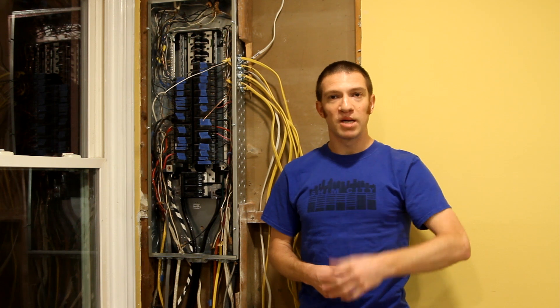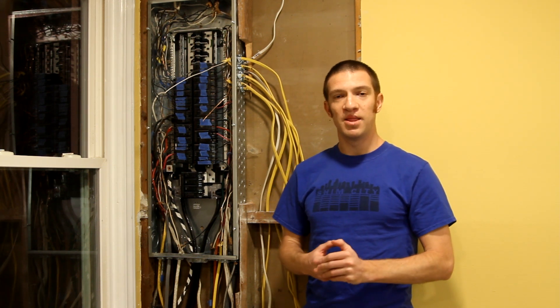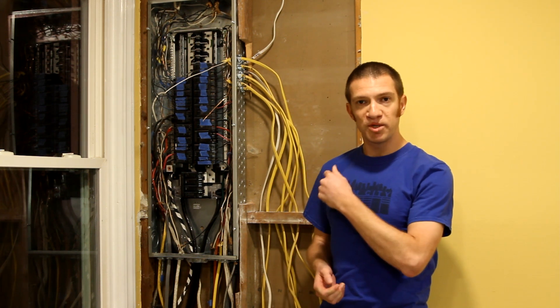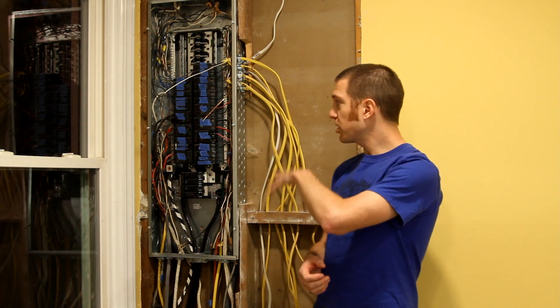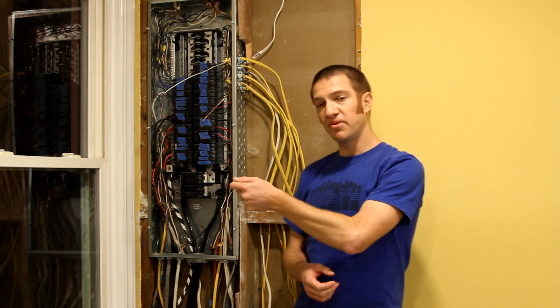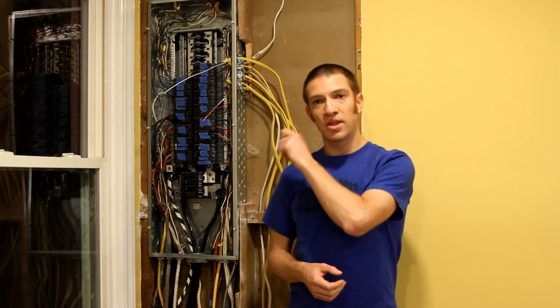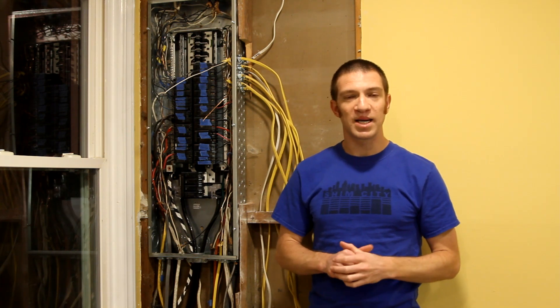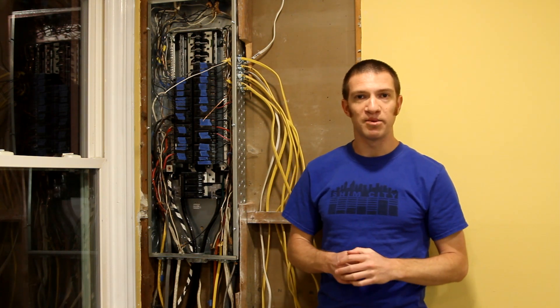We only had to wait a couple of hours to get the power turned back on for the house, and then you can start flipping your breakers on. I like to do all my breakers off, and then flip the main breaker on, and then flip them all on one at a time, so that if there is any short, then you kind of catch it on exactly where it happened, instead of being a mystery.